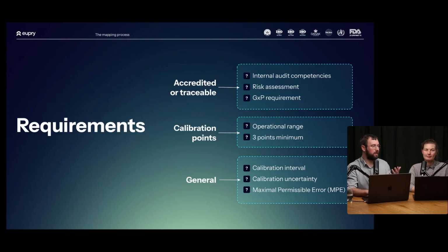I mean, could you have a situation where it could go lower? Could it go down to 0 degrees, for example? And if you have a door opening event, could it go above? You still need to capture the data there. In this stage, just think about it's important to know what are the interesting temperature points or humidity or CO2, whatever it might be, that you're going to experience through this process. Secondly, you always need to choose 3 points, and we'll go way more into detail with this in just a minute. And then lastly, in general, what's your calibration interval?